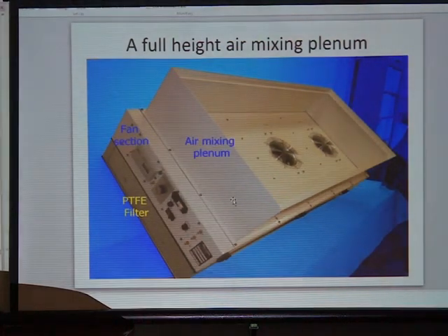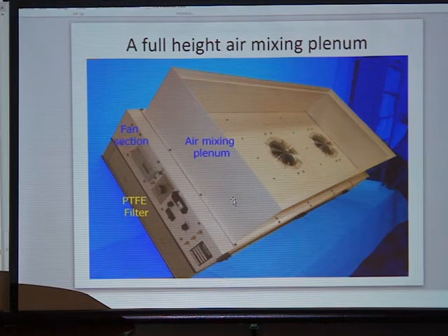Here's a fan filter that's actually one that is in manufacture today, and you can see how tall the air mixing plenum is, and this entire top area here has a large AMC filter in it that's, as you can see, roughly the same size as the fan filter itself. So that's a good design, and that one works well.